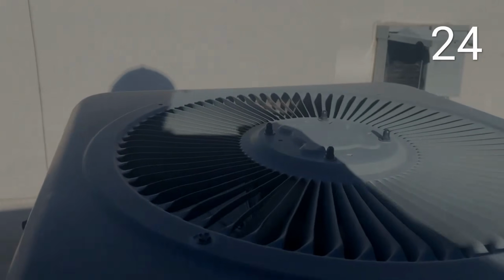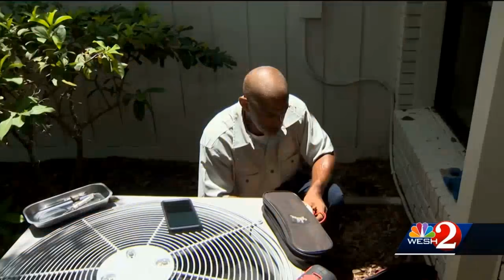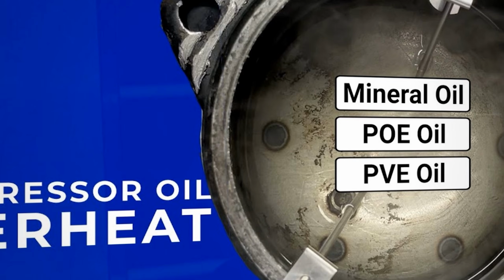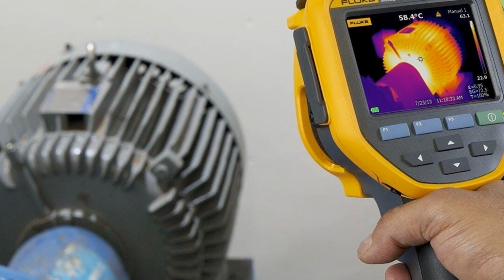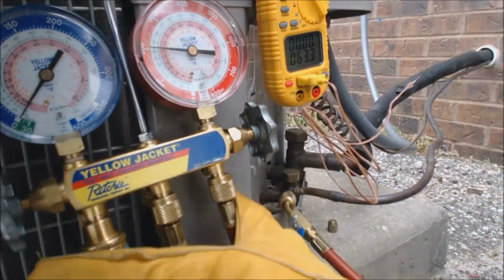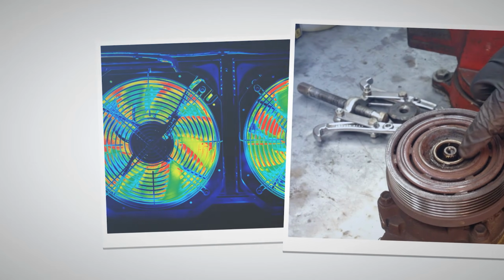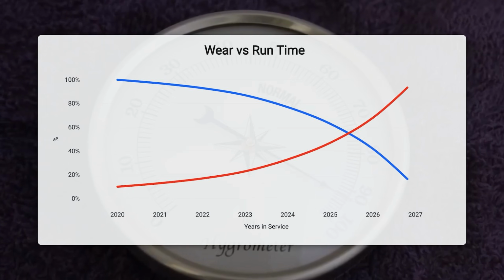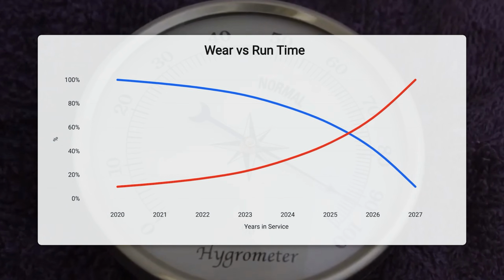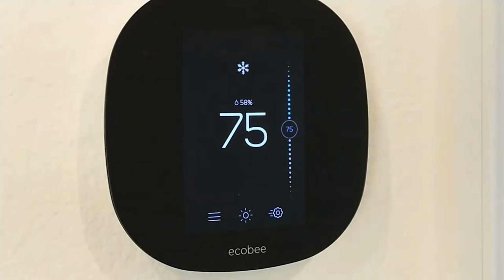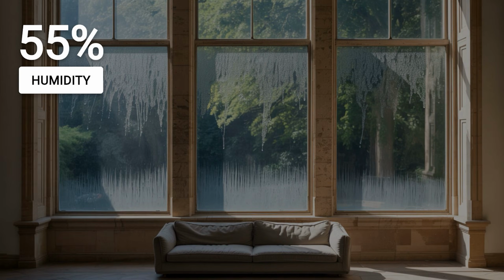An undersized compressor does not get that rest. On a hot day in Florida or Texas or Nevada, it runs continuously for hours. The oil breaks down under sustained heat. The windings overheat. The refrigerant charge becomes unstable. The system that should last 15 to 20 years is now burning through its mechanical life at double the designed rate. The evaporator coil compounds the problem. When a coil is undersized relative to the home's latent load, the moisture load in the air, it cannot remove enough humidity before the thermostat is satisfied on temperature. The air feels cold enough, but it is still saturated. Indoor relative humidity climbs above 55%. Above 60%.